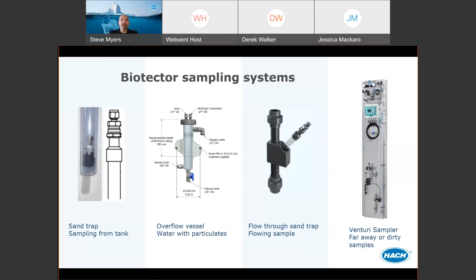So based on what is the challenge of that influent, is it fats and greases that float to the top? Is it sand and grit that sink? Combinations of the two, or is it a location issue where we just can't put the unit where it is convenient and we have to pull a sample a relatively long distance? We have a lot of options for sample delivery and sample conditioning. So whether it's sand traps, or on the right here is a Venturi sampler. This allows us to bring in, even with solid particles, a decent volume of sample from very long distances up to 40 meters or about a couple hundred feet almost distance away to the unit itself.